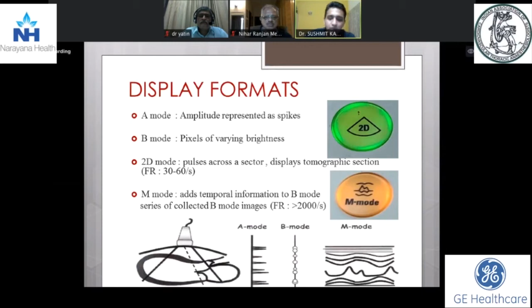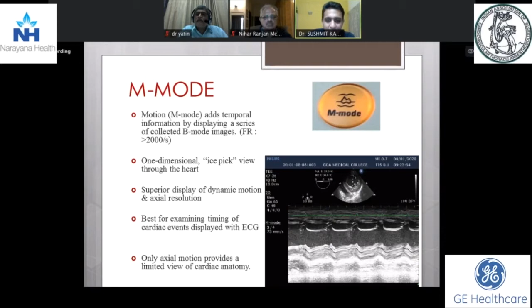And in M mode, we can add temporal information by displaying a series of collected B modes over time, with a very high frame rate of 2000 frames per second. So this gives us a one-dimensional ice pick view through the heart, and it gives us a superior display of dynamic motion and axial resolution. M mode is the best mode for examining timing of a particular cardiac event, which can be displayed with an ECG. One of the drawbacks of M mode is that it can only sense axial motion, so it gives a limited view of the anatomy. It does not give the lateral motion which can be given to us by 2D echocardiography.